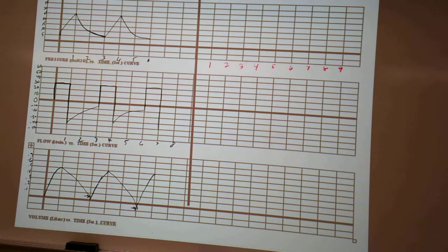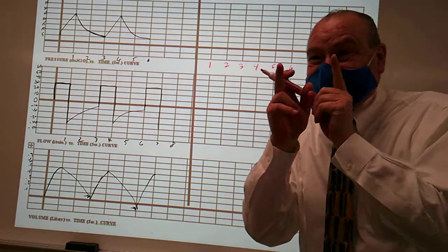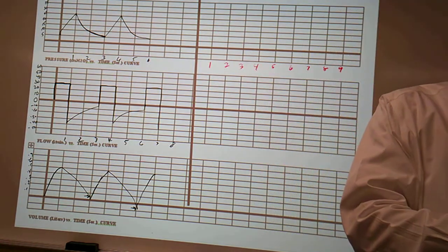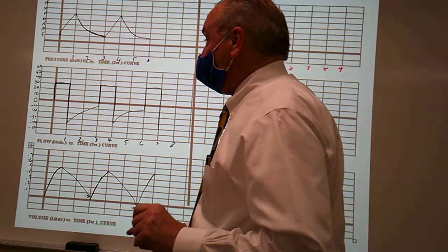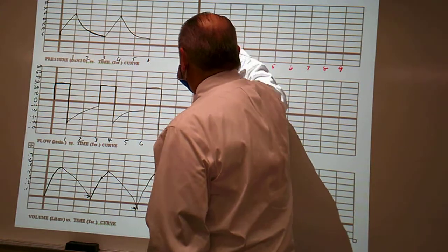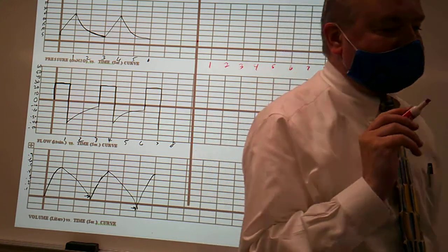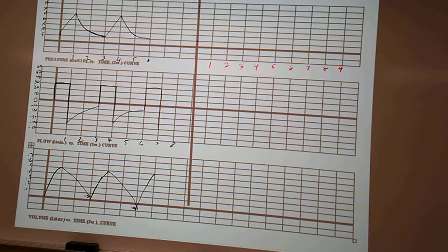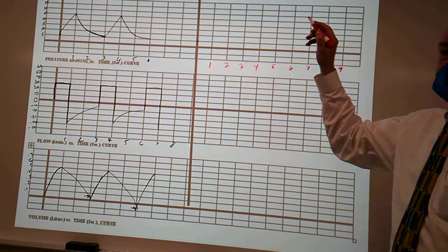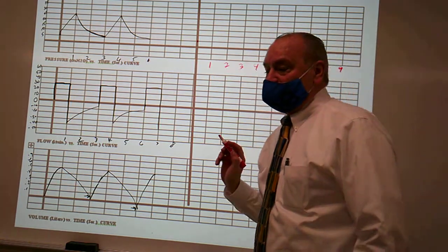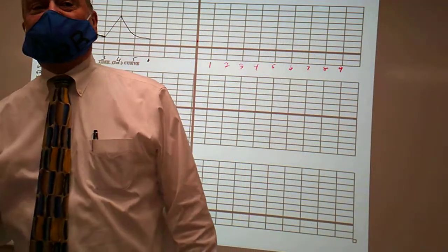If it says set, that's a different picture. If I have this set up with 5 as baseline and a set pressure of 20, it's going to go from 5 to 25. If I have an observed pressure of 25, that means my delta is only 20.